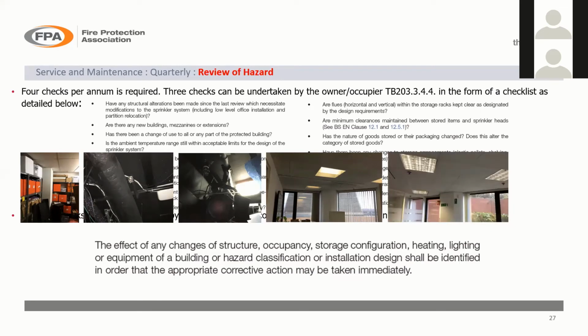The fifth picture on there, you can just see a glass partition in the bottom left-hand corner which has been put in, and beyond that is a sprinkler head. The glass partition's gone in after the sprinklers. It means the sprinklers on this side are now too far from the glazing. They're probably about 2.5 to 3 metres off that glazing, so they'll be pretty ineffective in that part of the building. And that should be picked up by a review of hazard.